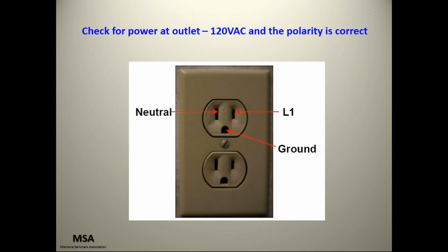Obviously, the first thing you want to check is for power at the outlet. You want to have 120 volts thereabouts. Excuse me. And the polarity should be correct. Okay, the little one here is the hot line, the big one, neutral, and of course your ground socket or ground plug.